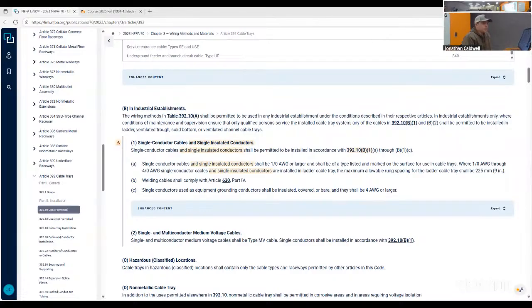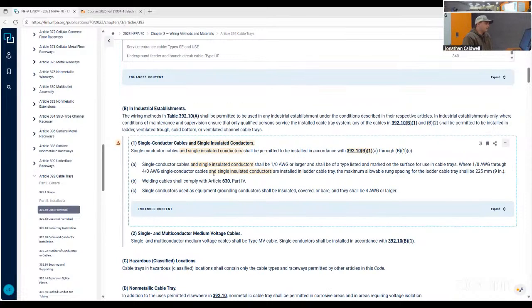So for my coworkers, now you see where the 9-inch part comes into play. Because they want to be able to run single conductors in those trays if they need to. And then welding cables shall comply. And then single conductors used as equipment grounding conductors shall be insulated, covered, or bare, and they shall be number 4 or larger. We don't have to worry about that because we typically run 4/0 through all of those trays and then tap off.